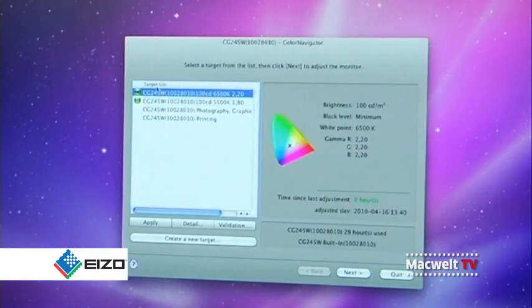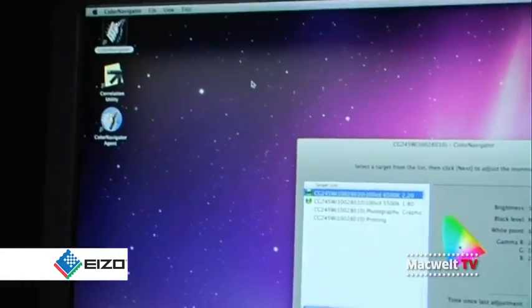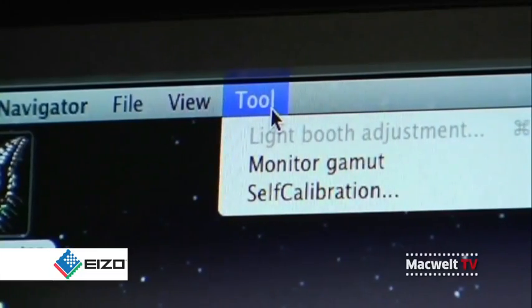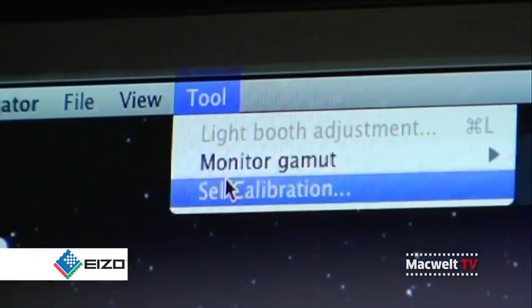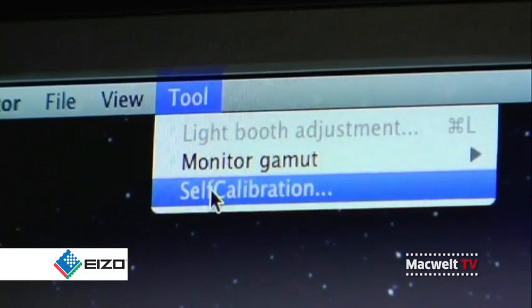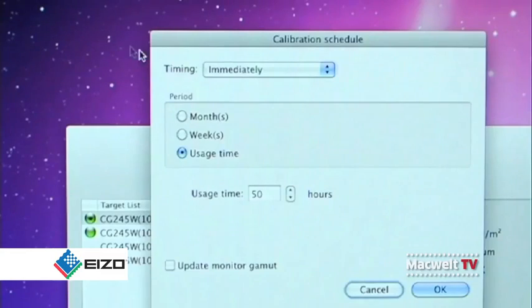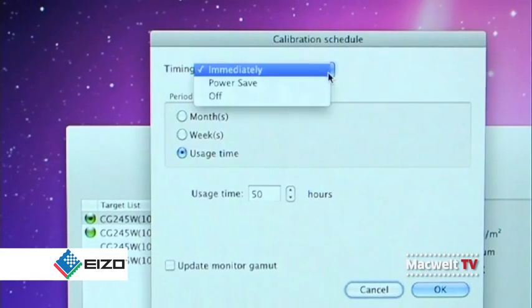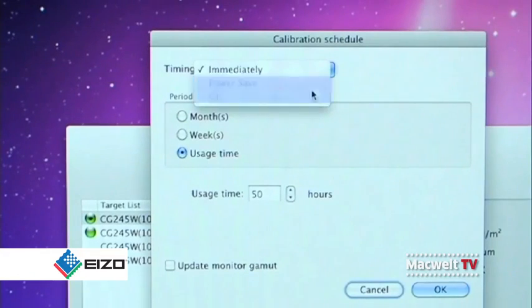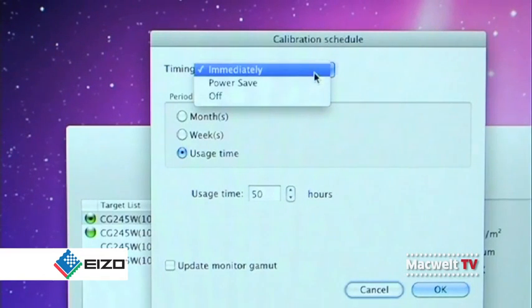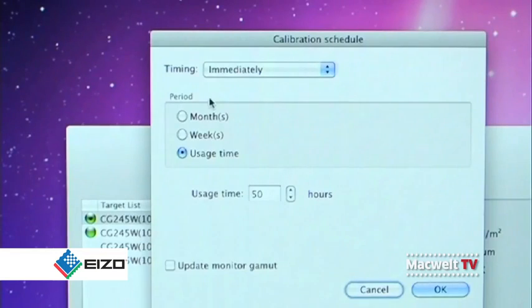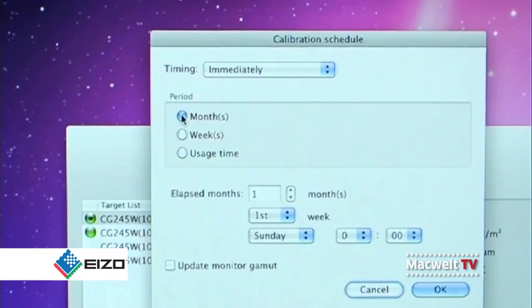The CG245W can also calibrate itself without the user doing anything. To do that, you create a schedule for the calibration under Self-Calibration in the Tools menu. You'll have various options for this. Immediately means that the monitor will calibrate itself, even if it's being used at the time. If you don't want that, you should select the Power Save setting, or Off. Here, the screen waits until it's in sleep mode or switched off.